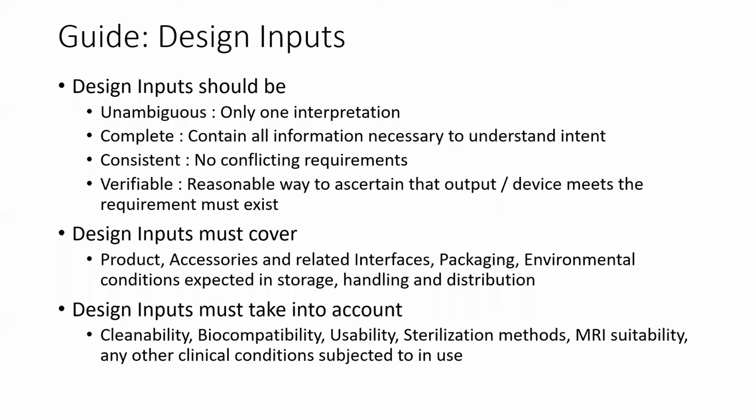So if you write a design input as a person who is let's say the ideator, and then you pass on this written document to your engineer, he should be able to work with this statement, understand it, and create a design output. So that is what it means when it says it has to be complete. It has to be consistent. So you can't write a design input which either at the beginning of the sentence says something which is at variance with the end of the sentence, or design input number 3 clashes with design input number 17. Okay, so that's very important that inputs have to be consistent.